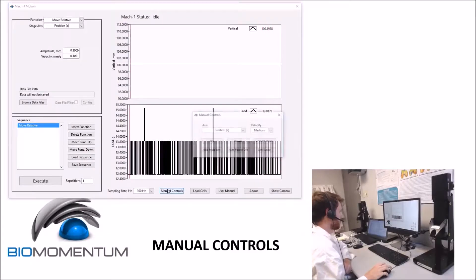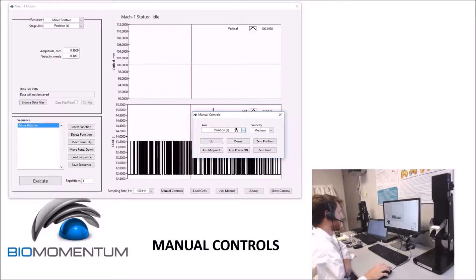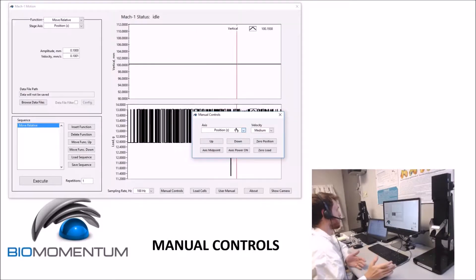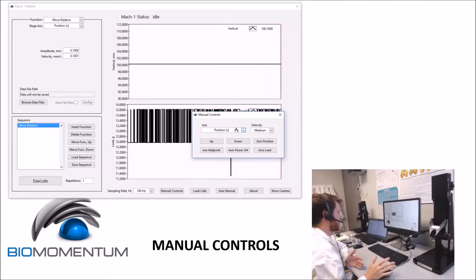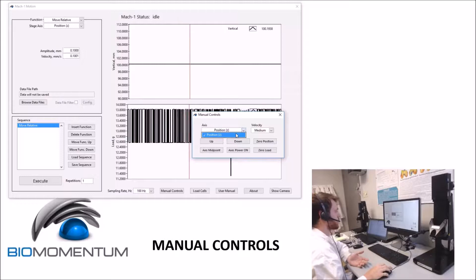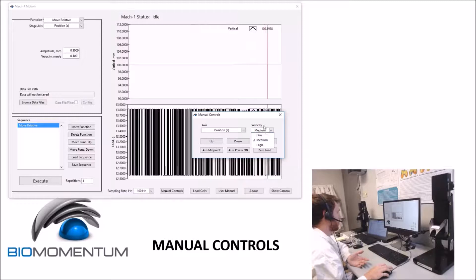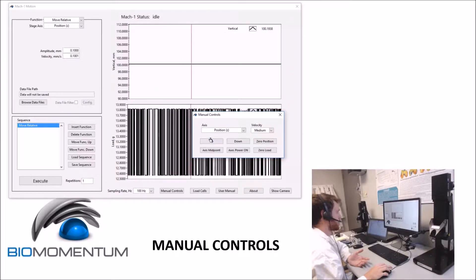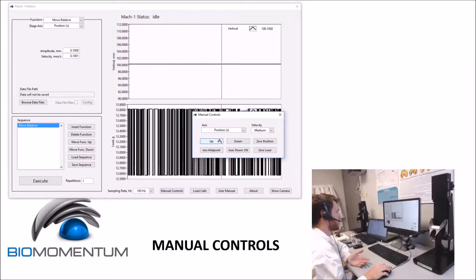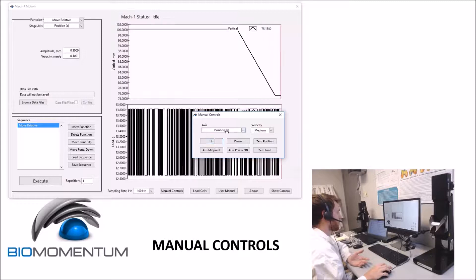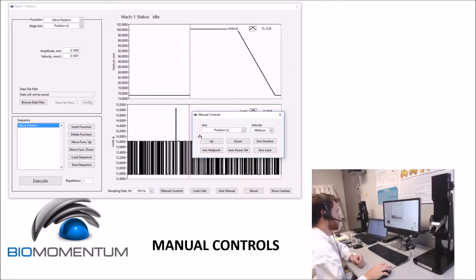Clicking the Manual Controls button will open a window that allows manual control of each stage's displacement. As each stage can move rapidly, be careful not to overload the load cell during this process by accidental metal-on-metal contact. On multi-axis systems, the user must choose which axis to move from the drop-down menu, and then three preset velocities are available: high, medium, and low. Clicking and holding a direction button results in the displacement of the corresponding stage in the chosen direction. For example, position Z in the up direction. Avoid fast repetitive clicking of the displacement buttons for more precision as all clicks result in displacements.